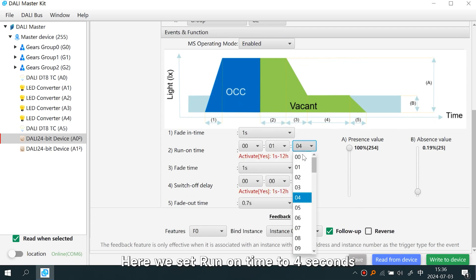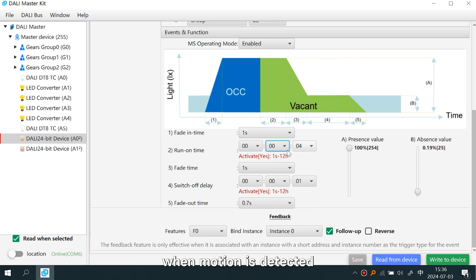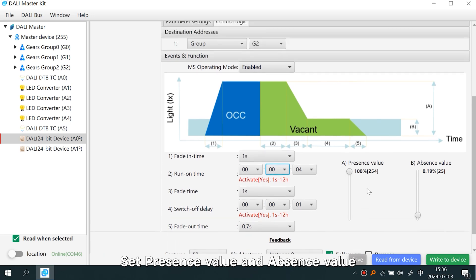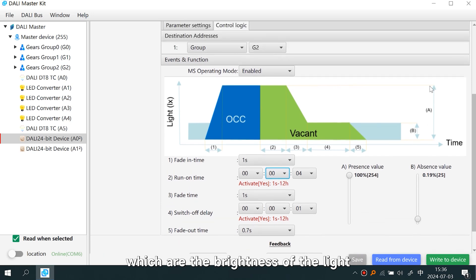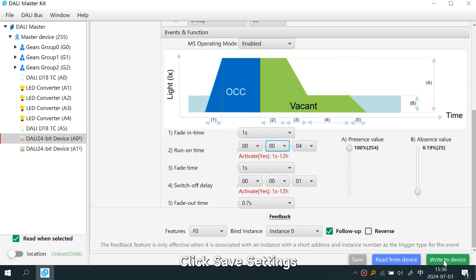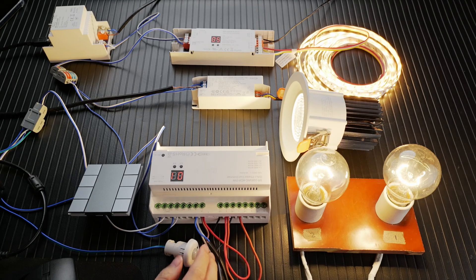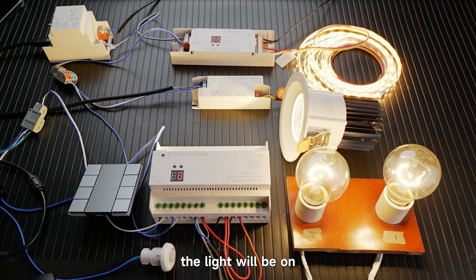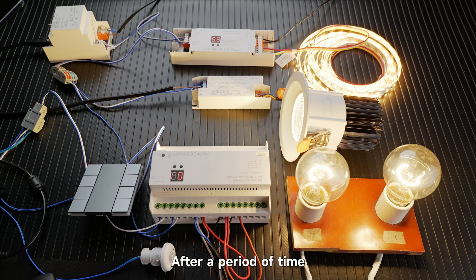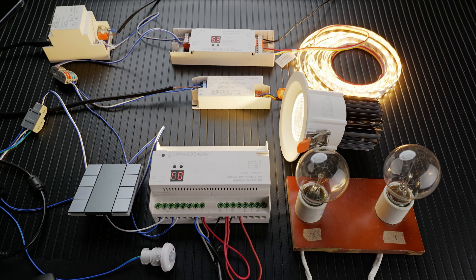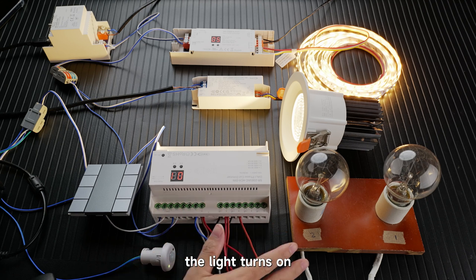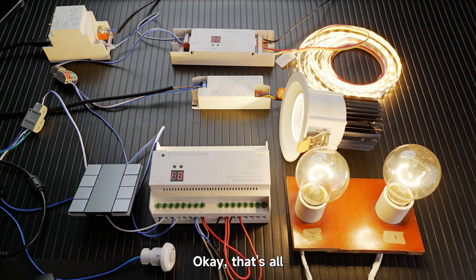Set run on time to four seconds — when motion is detected, the light will stay on for four seconds. Set the presence value and absence value, which define the brightness of the light. Click Save Settings. When motion is detected the light comes on, then stays on for a while. After the run-on period expires, the light goes off. When motion is detected again, the light turns back on.